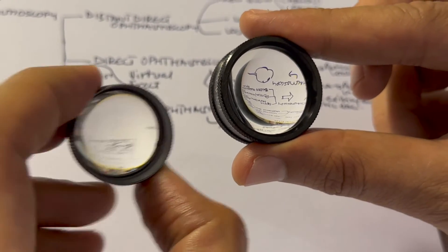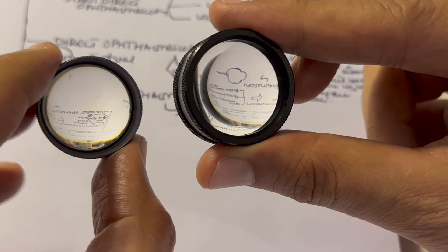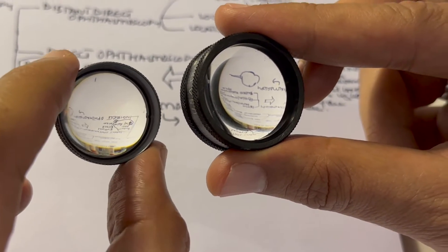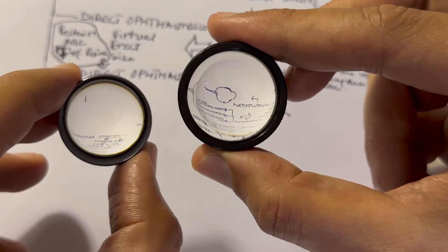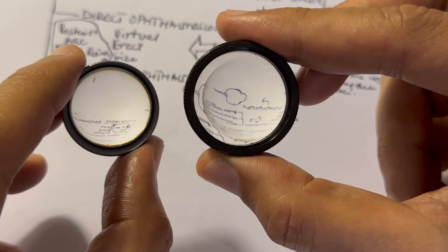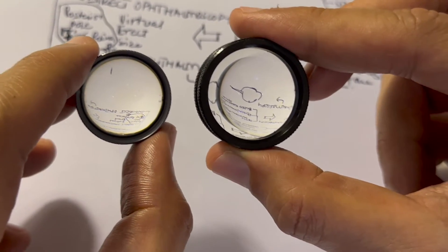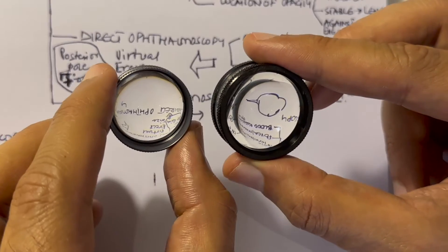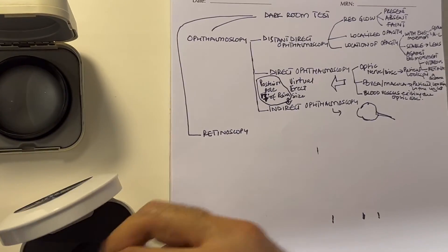You can also use a 78-diopter lens when using the slit lamp. The difference between a super field or 90-diopter lens and a 78-diopter lens is that in the 90-diopter lens the image is minified but the field of vision is more, whereas in the 78-diopter lens the image is bigger but the field is smaller. However, in both lenses the image is inverted and real.